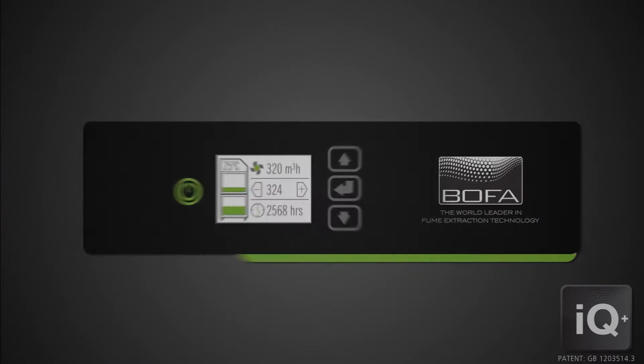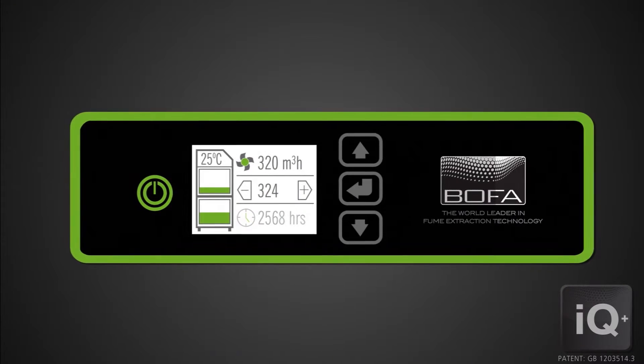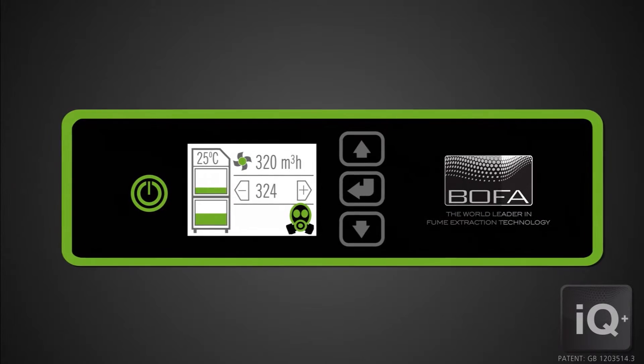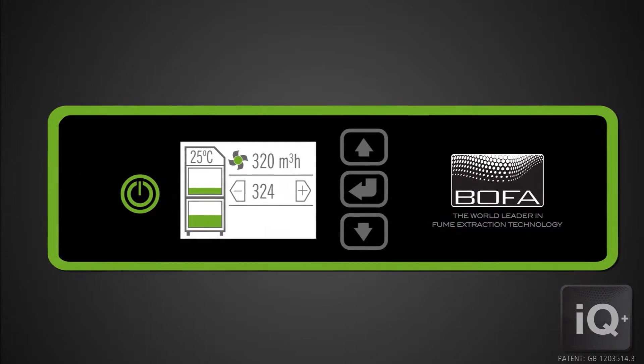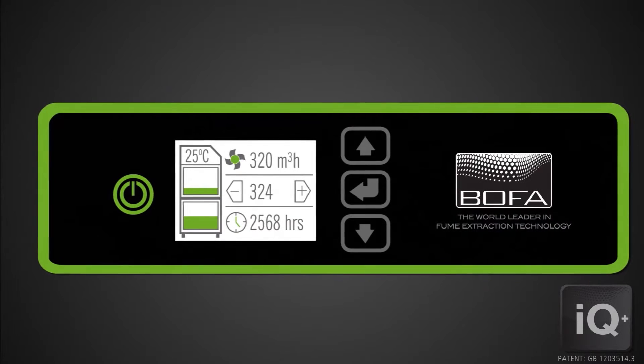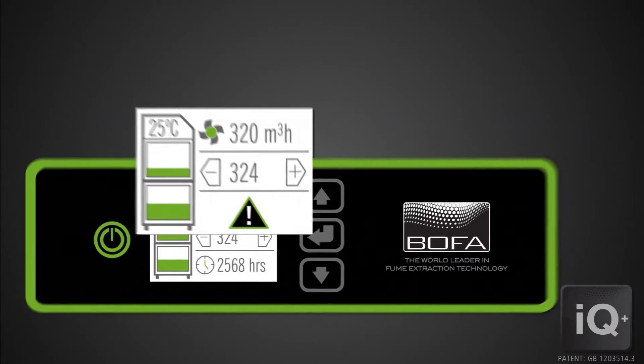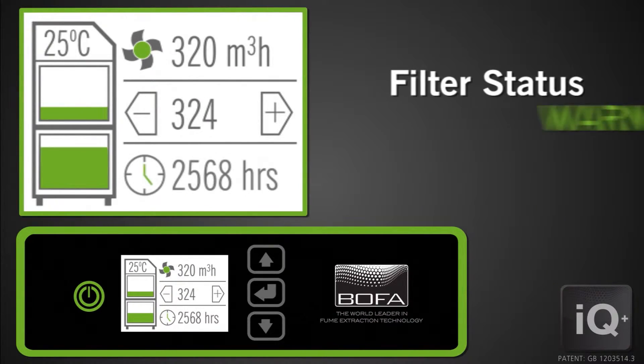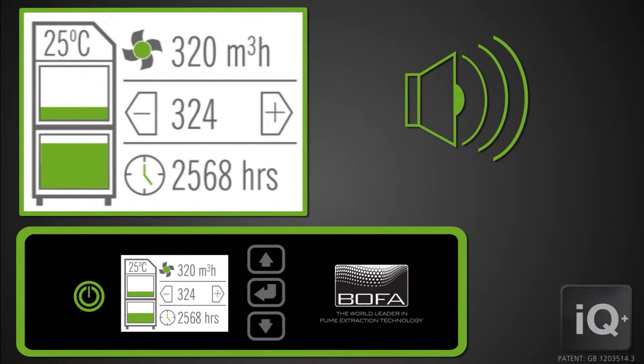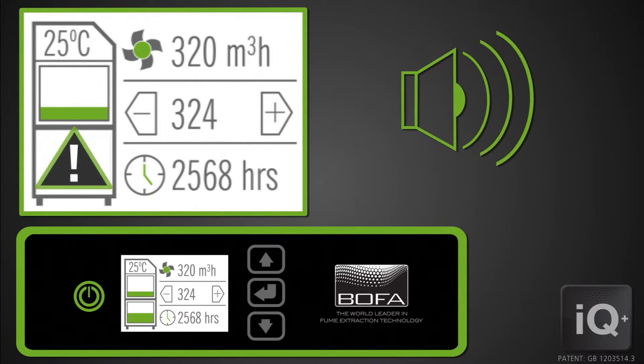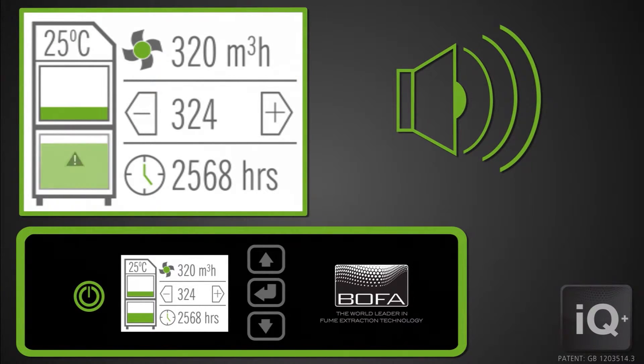The IQ provides a series of visual, audible and electrical outputs to ensure that all events are clearly communicated and that timely and appropriate intervention can be undertaken to maximise production uptime. The 100% alarm indicates that the filter is blocked and requires changing. An audible warning will sound and the representative filter status box on the display will confirm which filter should be replaced.